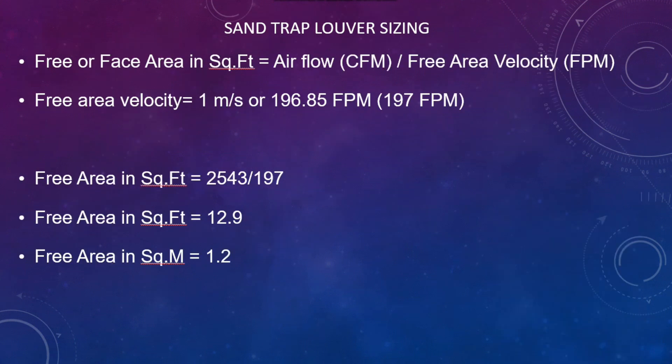The formula is: free air face area in square feet equals airflow in CFM divided by free area velocity in feet per minute, and the free area velocity is equal to 1 meter per second or 197 feet per minute.